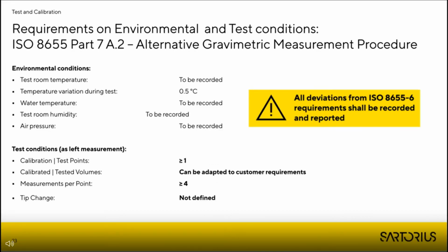When performing a test or calibration under Part 7A2, it is also possible to reduce the calibration points and to change the tested volumes, which means that the calibration no longer has to be performed at nominal volume, 50% and 10% of nominal volume. Here you are free to choose the volume where you want to have the pipette calibrated. Here it is also possible to change the number of measurements per test point, meaning fewer than 10 replicate measurements per test point are possible. So working under Part 7A2 really gives the user the freedom to adapt the test conditions to his specific needs.